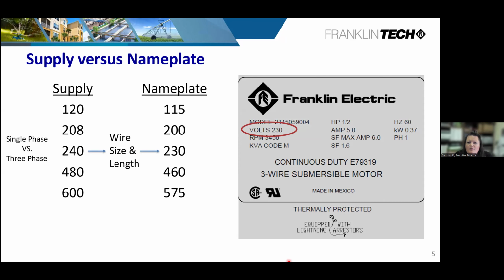And then there was a follow-up. So would it be appropriate and are you capable of adjusting the pump tech beyond the 253-volt threshold? Okay. So some of the products have a fixed standard, and that is deemed by the manufacturer. Pump tech is our product. I don't typically try to harp on our stuff too much, but there are a lot of protection products out there, and for the most part, the manufacturer knows that this is a fixed value, and so therefore there is no forgiveness. We know, and they know that if you go outside that realm, what's going to happen is you're just going to destroy the equipment.